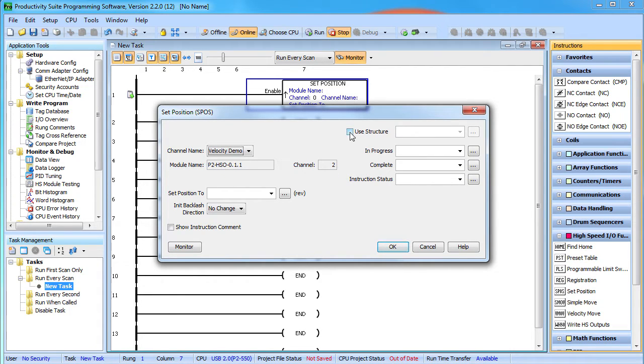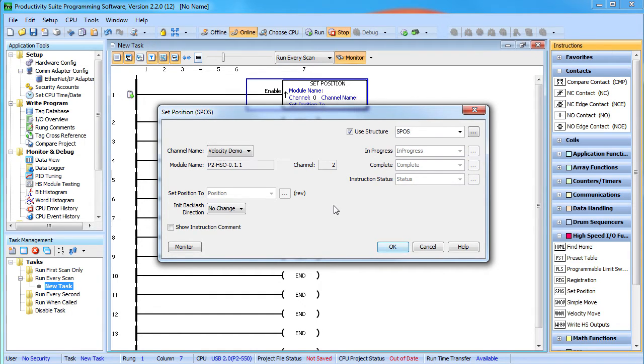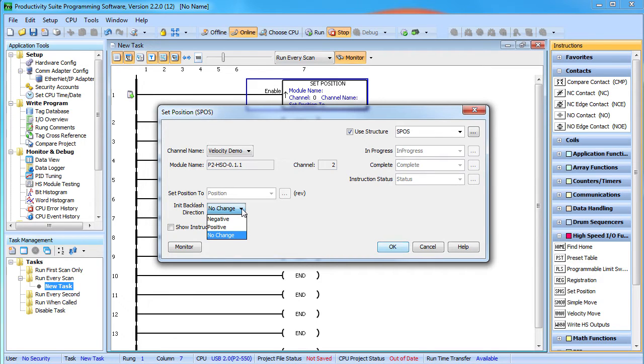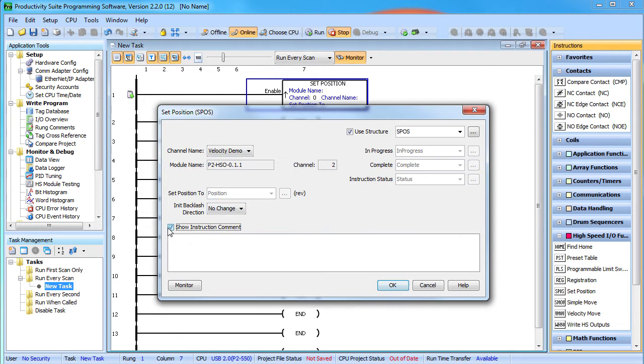We'll create a structure so we can easily modify the position in the data view or ladder code. You can also use this instruction to set the backlash direction. You would typically use this to set the initial backlash direction when initializing a system. We don't need it for this demo so we'll just leave it at no change. And you can add an instruction comment if you want to.